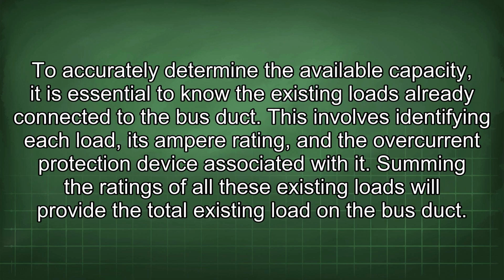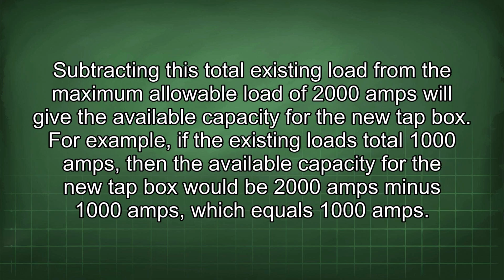To accurately determine the available capacity, it is essential to know the existing loads already connected to the bus duct. This involves identifying each load, its ampere rating, and the overcurrent protection device associated with it. Summing the ratings of all these existing loads will provide the total existing load in the bus duct. Subtracting this total existing load from the maximum allowable load of 2000 amps will give the available capacity for the new tap box. For example, if the existing loads total 1000 amps, then the available capacity for the new tap box would be 2000 amps minus 1000 amps, which equals 1000 amps.